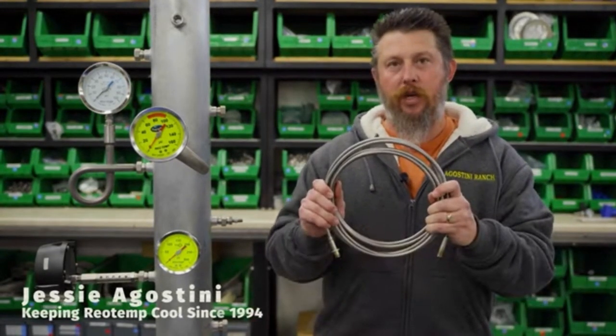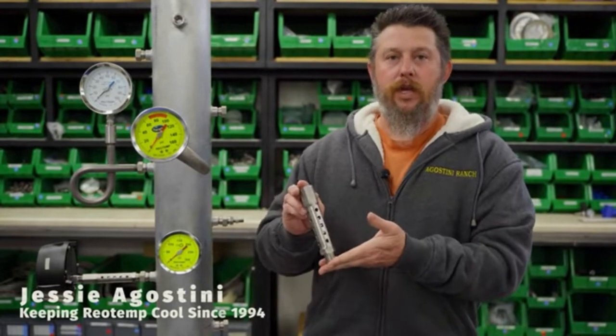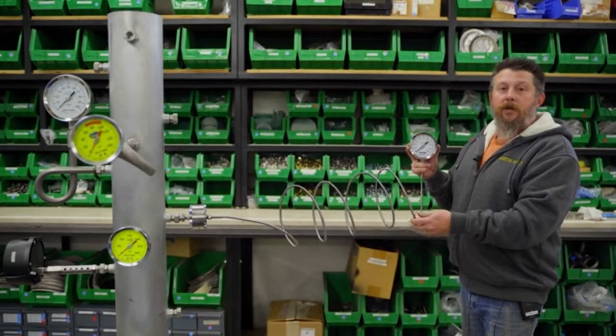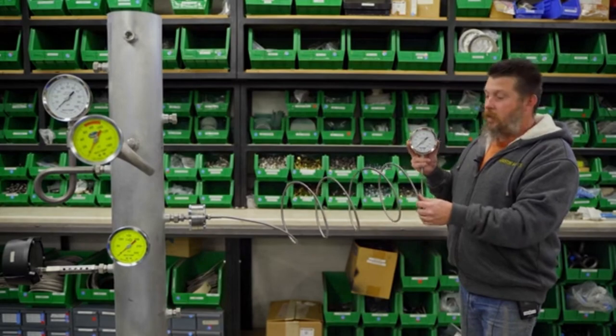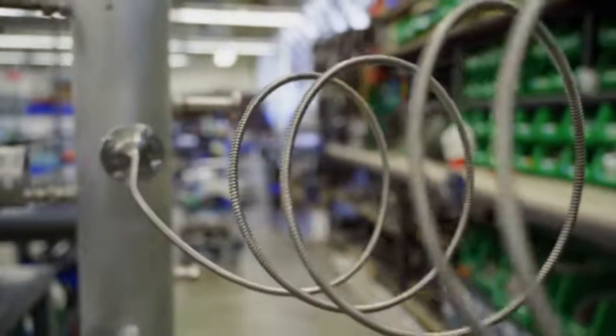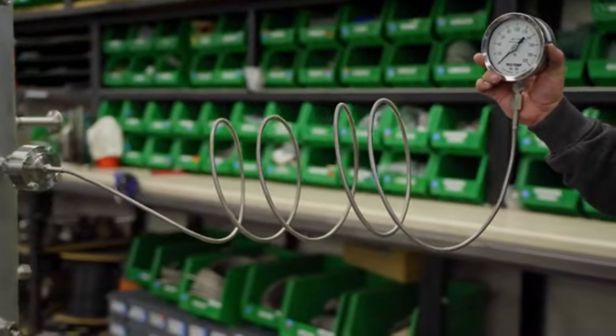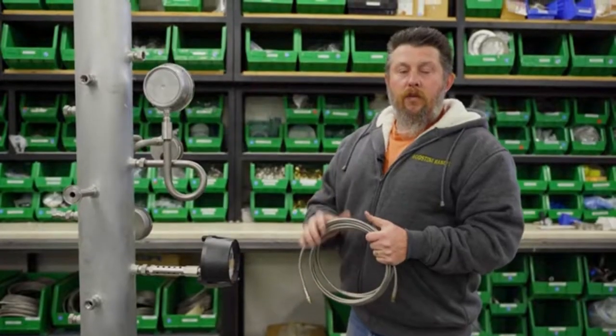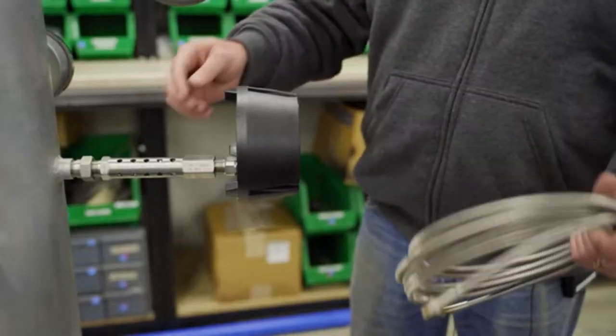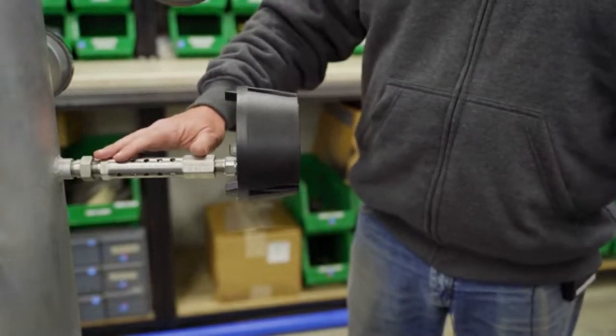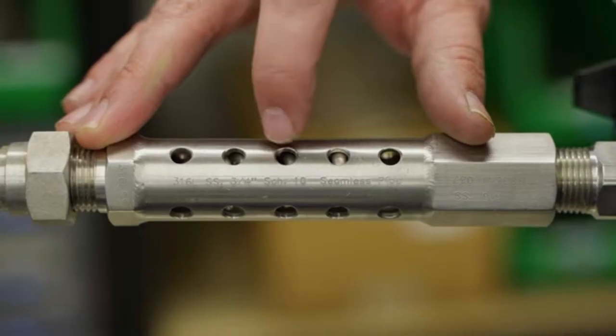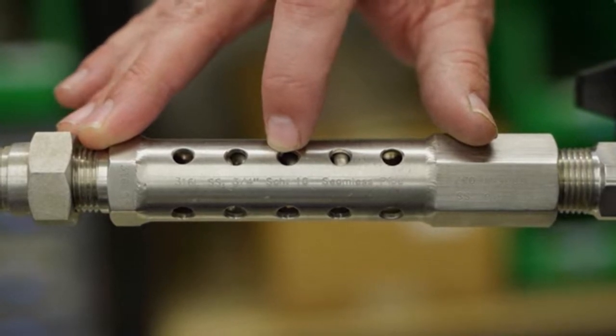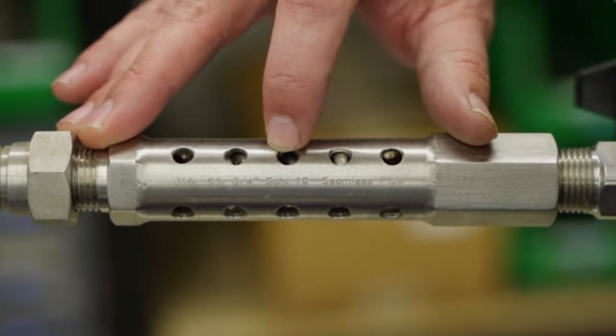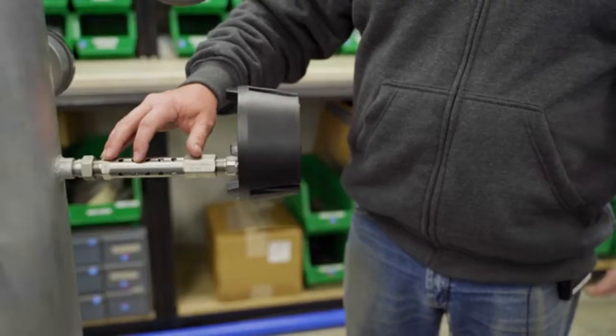For non-steam applications such as exhaust gas or hot oils, one might consider the use of capillary or cooling towers. If you plan to mount your instrument further away from the pipe or vessel, capillary like this can be used, which will allow you cooling of 150 degrees or more per foot. If you're looking for a more compact assembly, you may consider switching to something more like this, which is a cooling tower that employs a tightly coiled capillary system inside of a small rigid housing to perform roughly the same amount of cooling as 4 feet of capillary would.